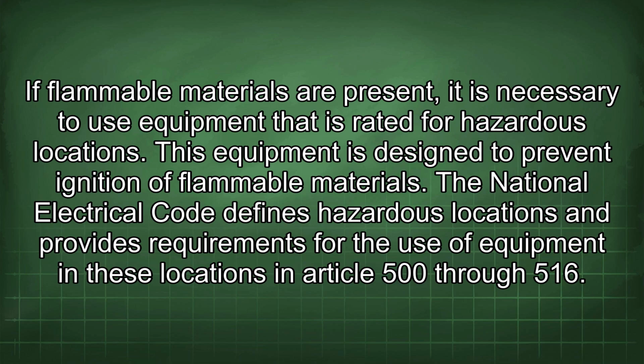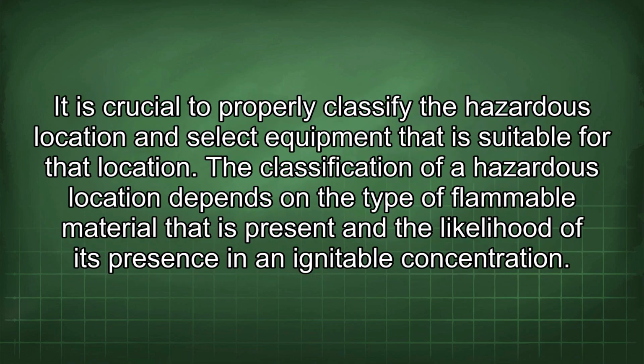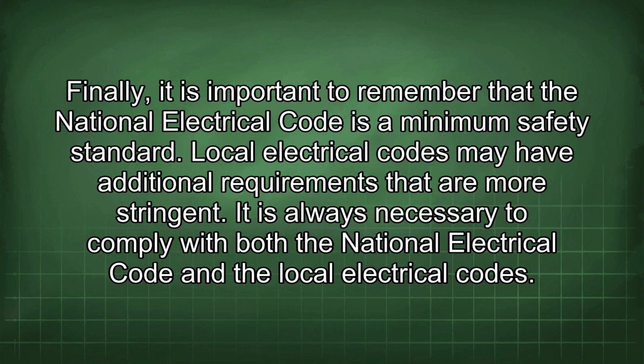The National Electrical Code defines hazardous locations and provides requirements for the use of equipment in these locations in Article 500 through 516. It is crucial to properly classify the hazardous location and select equipment that is suitable for that location. The classification of a hazardous location depends on the type of flammable material that is present and the likelihood of its presence in an ignitable concentration. Finally, it is important to remember that the National Electrical Code is a minimum safety standard. Local electrical codes may have additional requirements that are more stringent. It is always necessary to comply with both the National Electrical Code and the local electrical codes.